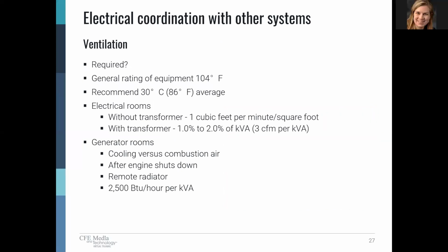So let's talk a little bit about coordination with your mechanical or HVAC engineers on ventilation and cooling of electrical rooms. Is it required, and how do you determine the amount of air and or cooling required? First off, understand that the general rating of electrical equipment, that is specifically electronic circuit breakers, is about 104 degrees Fahrenheit. If it gets hotter than that in the room, some of these protective devices can start to have malfunctions or accuracy issues. So that's kind of the upper limit, but you really don't want necessarily in an electrical room, a maintenance electrical room, for it to be 104. You've got maintenance people servicing those types of things.